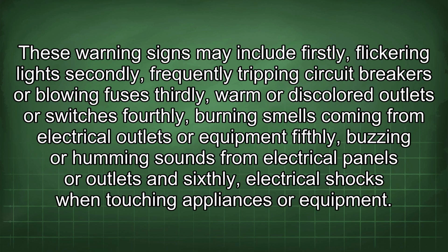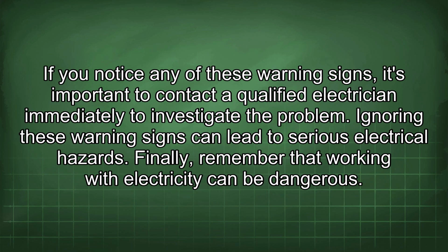These warning signs may include: firstly, flickering lights; secondly, frequently tripping circuit breakers or blowing fuses; thirdly, warm or discolored outlets or switches; fourthly, burning smells coming from electrical outlets or equipment; fifthly, buzzing or humming sounds from electrical panels or outlets; and sixthly, electrical shocks when touching appliances or equipment. If you notice any of these warning signs, it's important to contact a qualified electrician immediately to investigate the problem. Ignoring these warning signs can lead to serious electrical hazards.